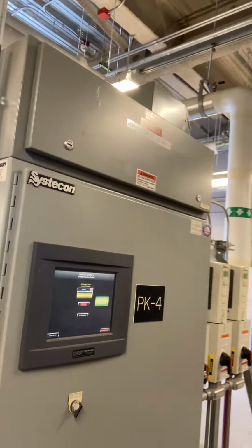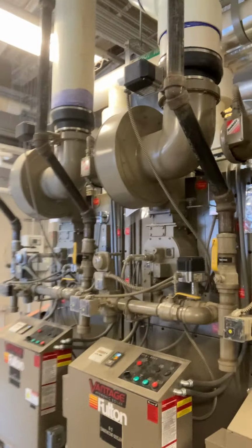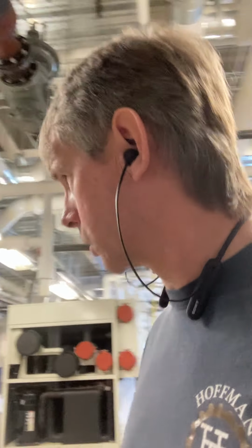And we've got some boilers that make heat for the building. We actually use heat in the summertime for what we call reheat. The VAV box may overcool because it needs a minimum amount of outside air being fed to it. So sometimes it could overcool the space, and we use hot water reheat. That's where heat recovery works really well with the chillers, because we can make chilled water and reject the heat back into the hot water loop of the building as opposed to sending it to the cooling towers, because that can be wasteful.